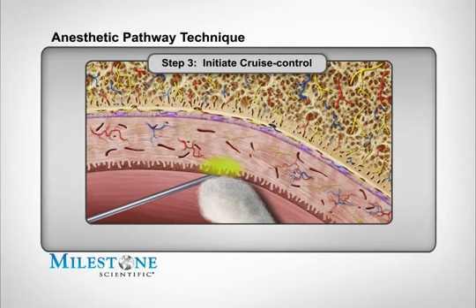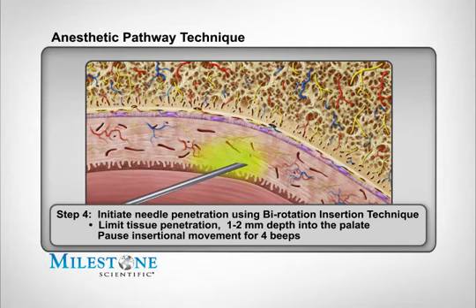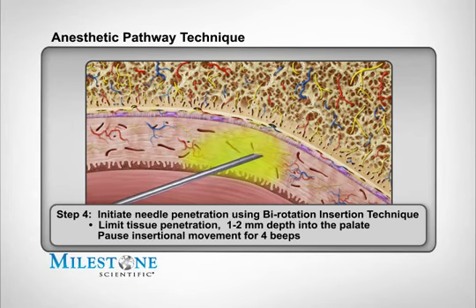Do not allow the needle to puncture the tissue at this time. Continue to allow the needle to stay on the surface for another five beeps before initiating needle penetration. Step 4: Rotate the handpiece back and forth with a slight forward movement to allow a shallow puncturing of the tissue to the depth of 1 to 2 millimeters. Then stop forward movement to allow the STA system to continue to deposit anesthetic for an additional 4 to 5 beeps before any further penetration of the tissue.